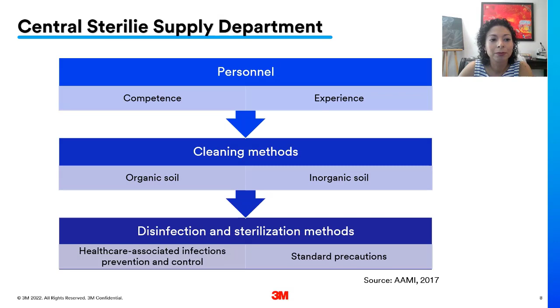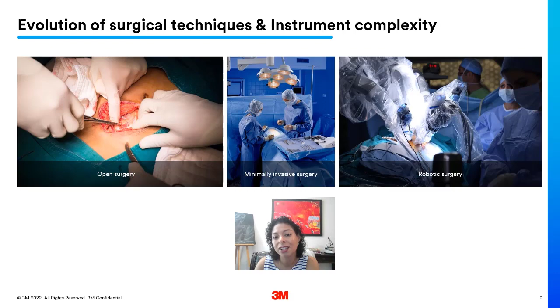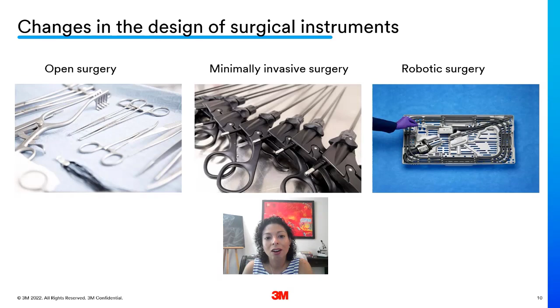The evolution of surgical techniques and medical devices is a big step forward in healthcare, and it's resulted in the improvement of quality for our patient care. Surgical instruments usually used in conventional surgical techniques are less complex for reprocessing, but with the arrival of minimally invasive surgery, including robotic surgeries, surgical instruments have become more complex and the cleaning processes have become a major challenge. And as a result, these challenges compromise subsequent steps such as sterilization and disinfection. The complexity of surgical instruments such as long and narrow lumens or lumens with crevices and joints make cleaning difficult and increase the risk of retaining organic residues and microorganisms that can cause or increase risks for infections. Whenever we have failures in cleaning medical devices, it reduces the effectiveness of disinfection and sterilization processes and favors cross-infections.